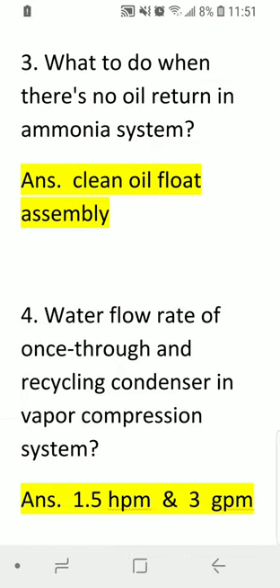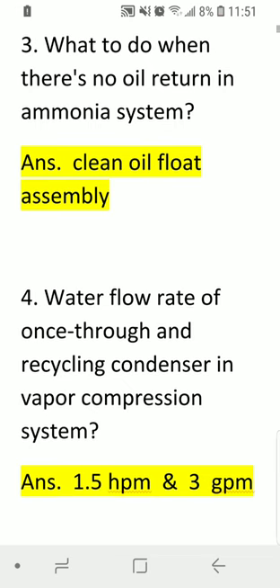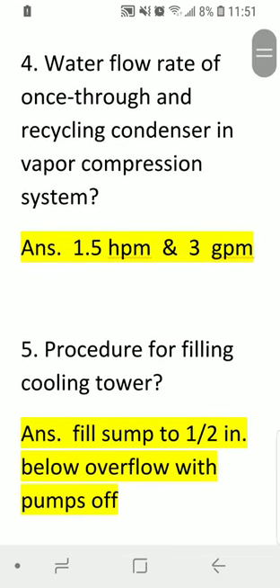Question three: what to do when there is no oil return in an ammonia system? Answer: clean the oil float assembly. Question four: what is the water flow rate for a once-through and recycling condenser in a vapor compression system? Answer: 1.5 GPM and 3 GPM.